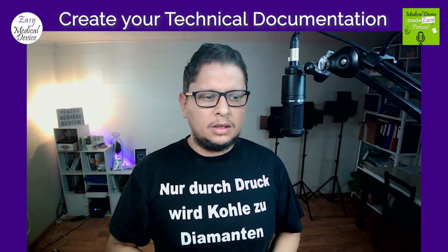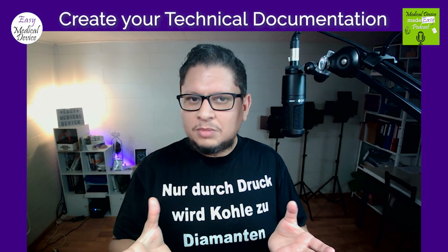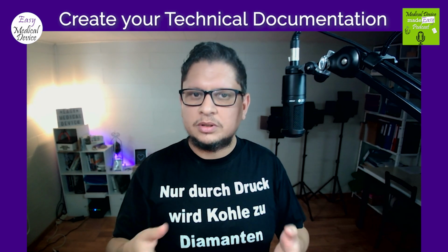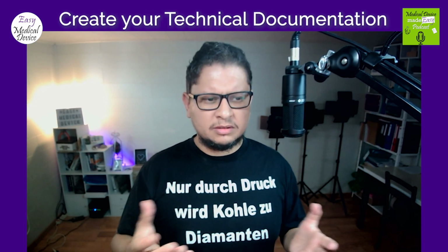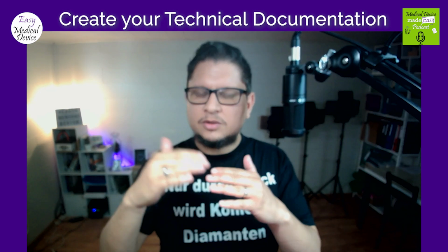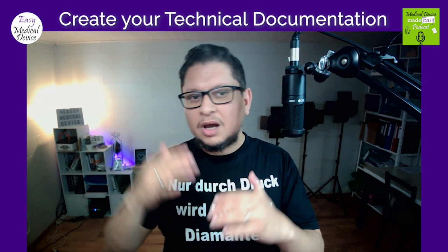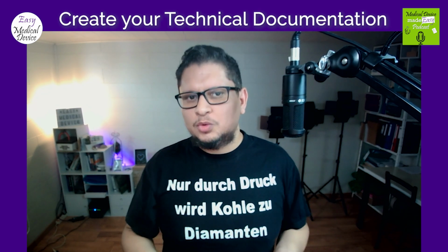For example, you have two elements in the technical file. You have the file, which is a Word document, which contains all the information that we'll go through now. And you have the second part, which is the annexes. There are some people, I saw that, who put everything in one file: the technical file plus all the annexes, Annex 1, Annex 2, Annex 3, etc., in one PDF, which for me is not really the right method.